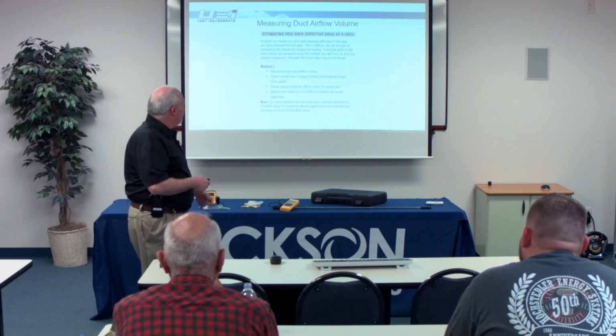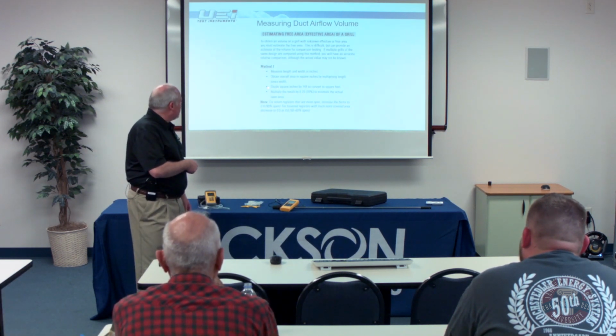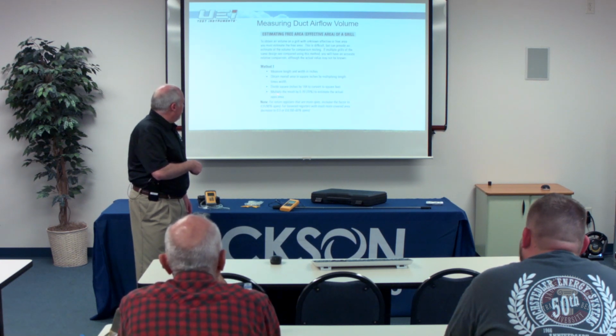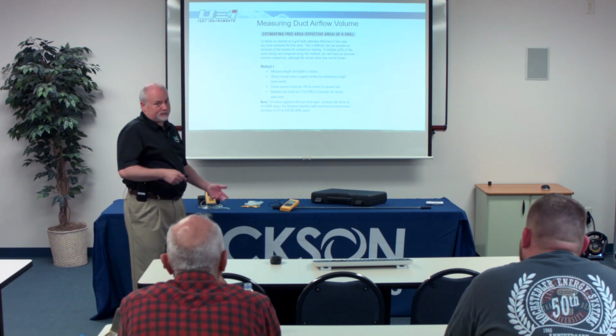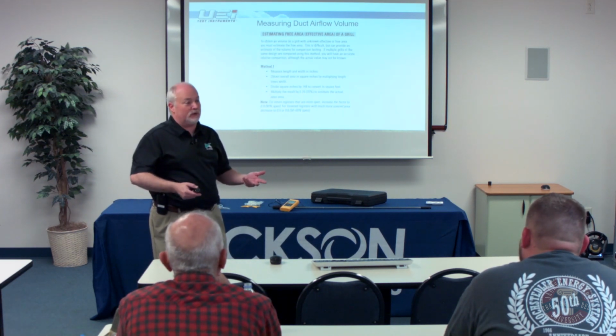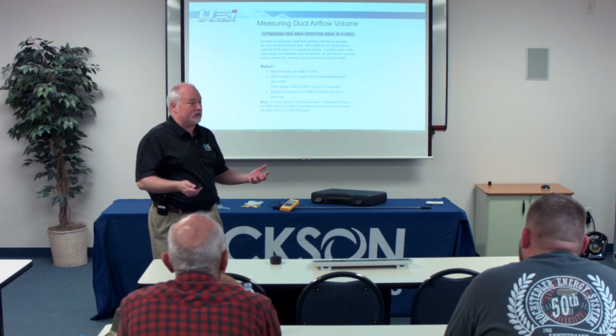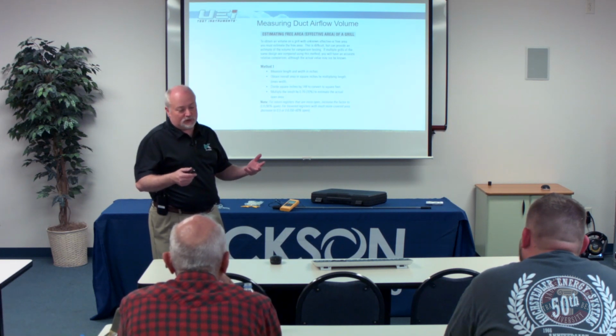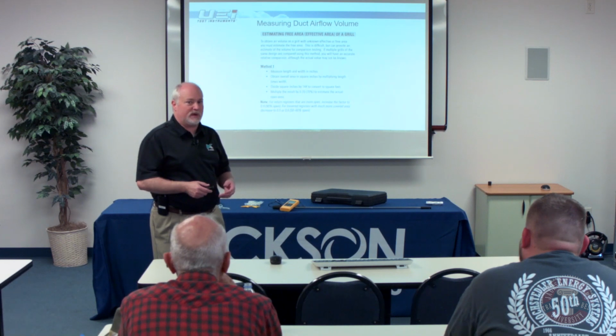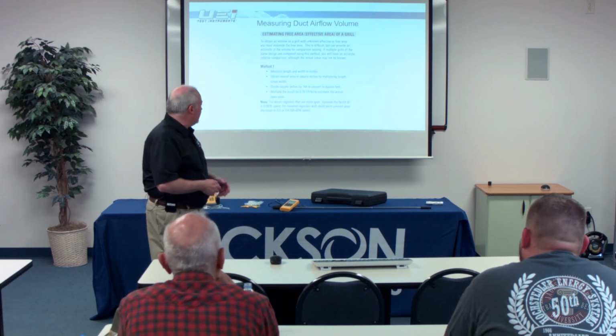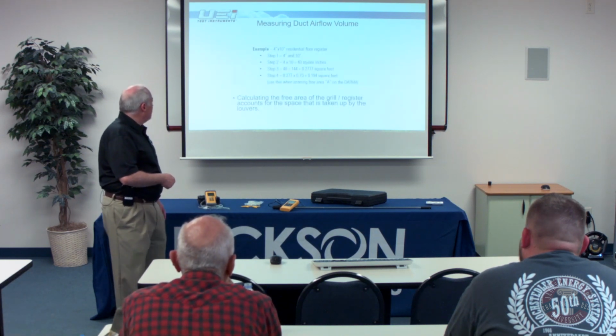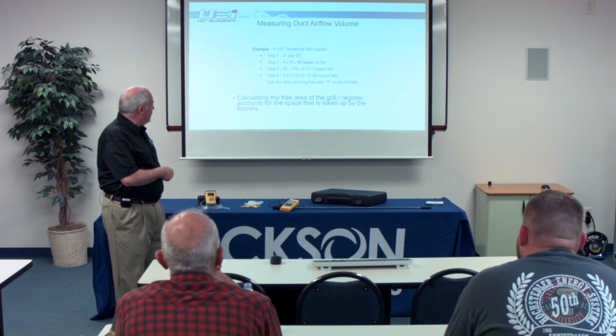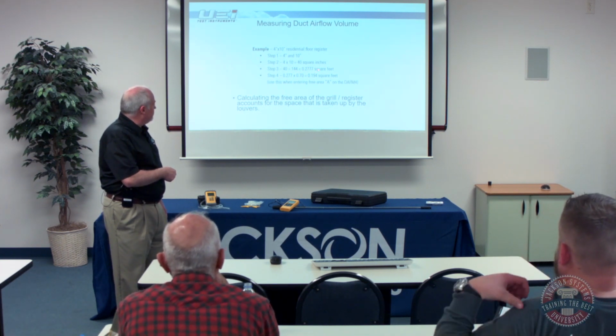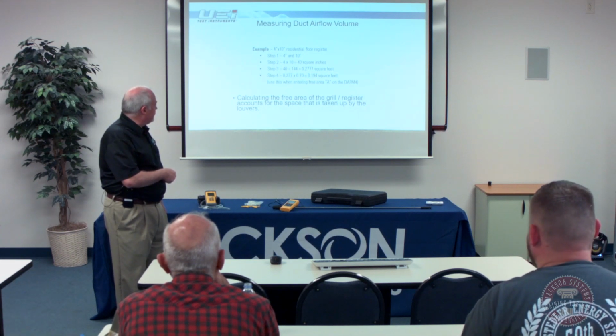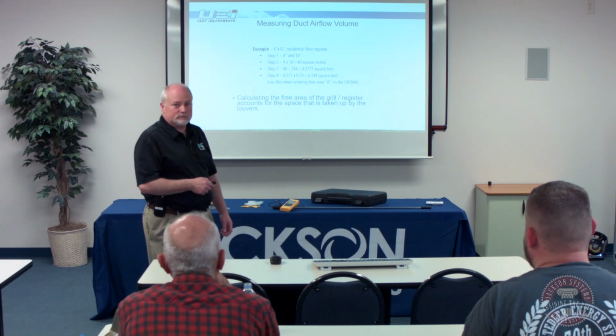All right. So for our grills, we're going to figure up our square inches, convert that to feet, and then multiply that by either our 0.7, which is pretty common for a metal grill, or some wooden decorative grills can be as low as 0.4. So they've only got 40% free airspace. Hopefully you can identify that grill and look at the manufacturer specs to see its free area, to give you the most accurate reading for that adjustment. So if we had a 4x10 residential floor register, 4 times 10 is 40 square inches, 40 divided by 144 to convert that to square feet gives us the area we want to enter when we're calculating that for a grill.